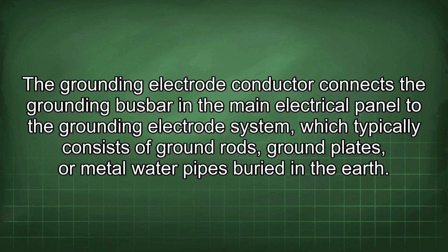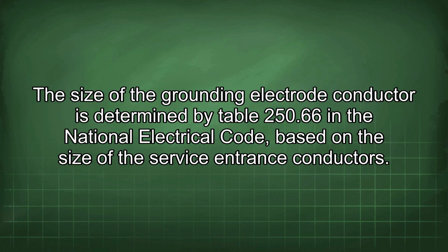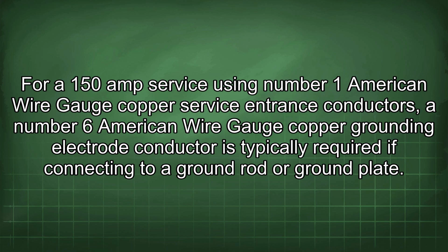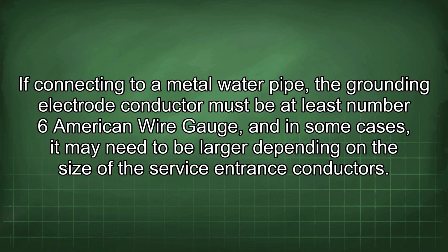The grounding electrode conductor connects the grounding busbar in the main electrical panel to the grounding electrode system, which typically consists of ground rods, ground plates, or metal water pipes buried in the earth. The size of the grounding electrode conductor is determined by Table 250.66 in the National Electrical Code, based on the size of the service entrance conductors. For a 150 amp service using number 1 American wire gauge copper service entrance conductors, a number 6 American wire gauge copper grounding electrode conductor is typically required if connecting to a ground rod or ground plate. If connecting to a metal water pipe, the grounding electrode conductor must be at least number 6 American wire gauge, and in some cases, it may need to be larger depending on the size of the service entrance conductors.